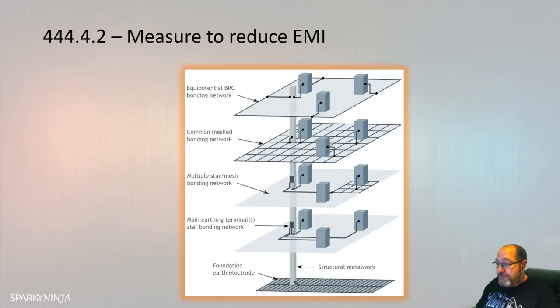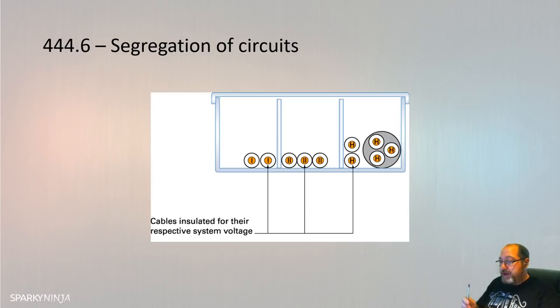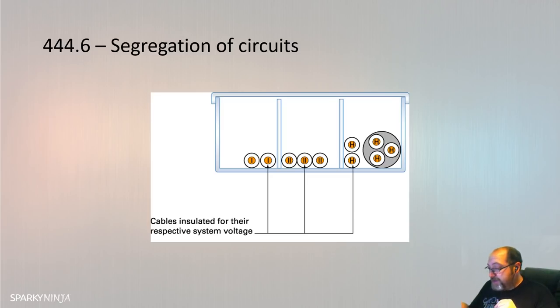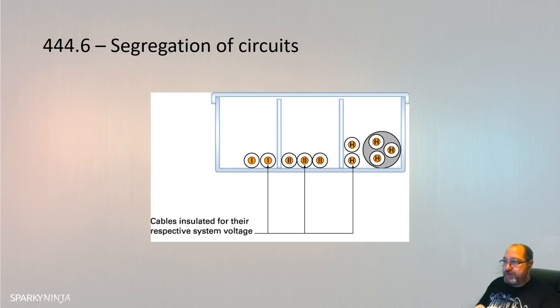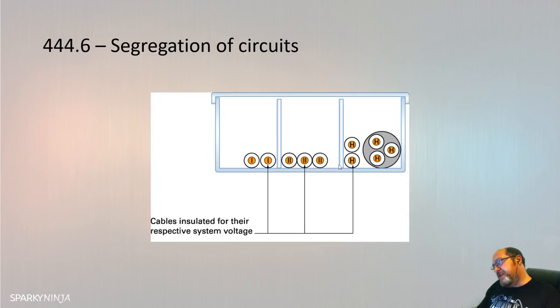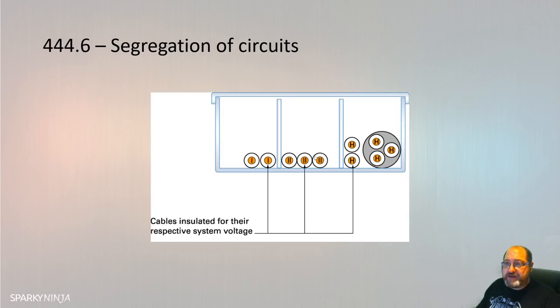Section 444.6 covers segregation of circuits. Cables used at band two voltage (low voltage) and cables used at band one voltage (extra-low voltage, such as SELV) which share the same cable management system or route shall be installed according to the requirements of 528.1 and 528.2, which we'll cover in chapter 52. It's all about segregation — for example, a dado trunking in an office or school with power in one compartment and data in the other — to reduce electromagnetic interference.